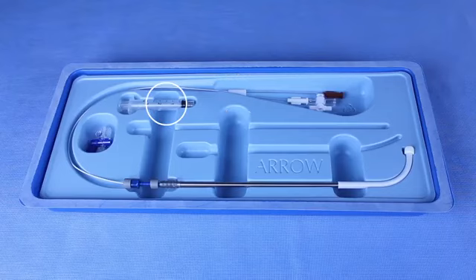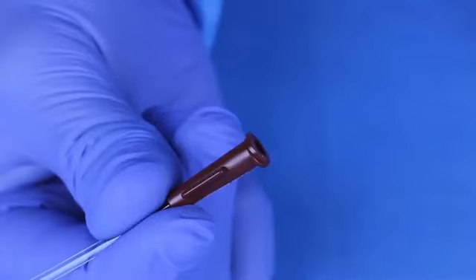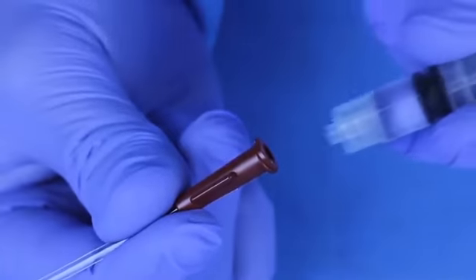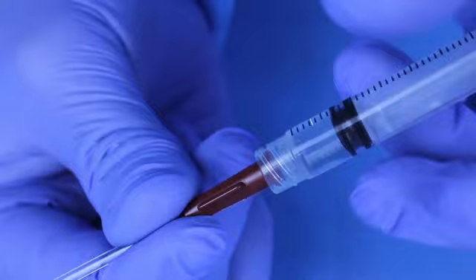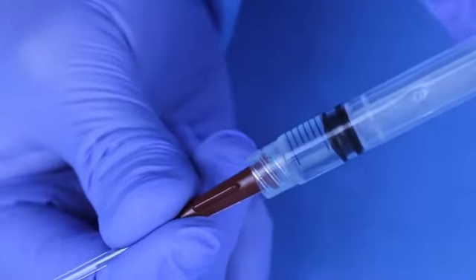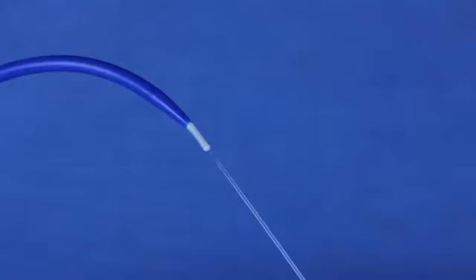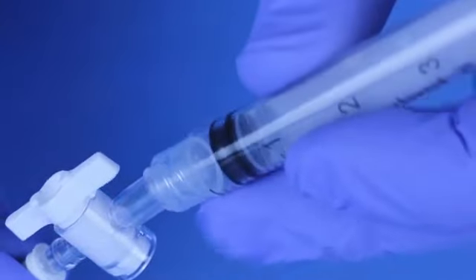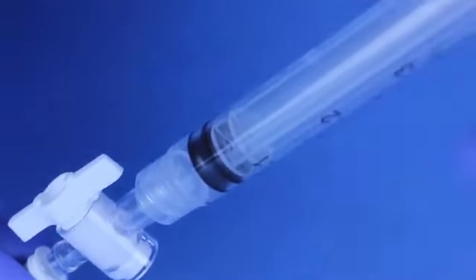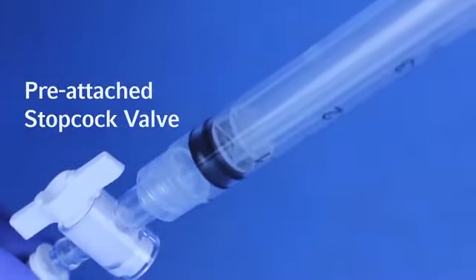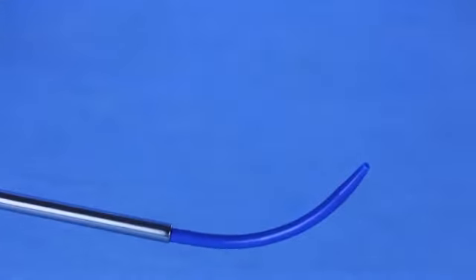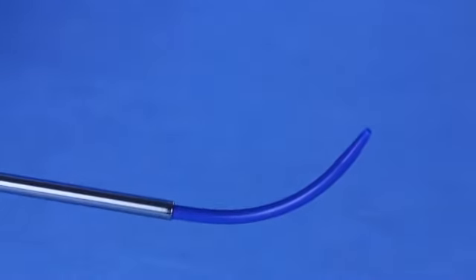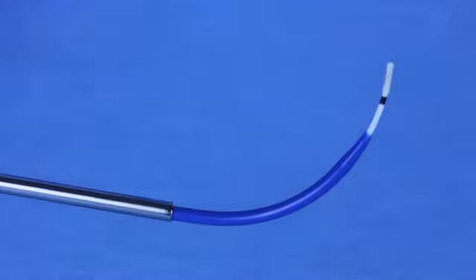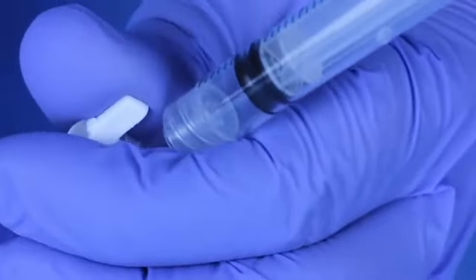catheter, 1 1/4 milliliter control stroke syringe, 3-way stopcock. Flush infusion port of balloon catheter and any attached tubing or stopcock with sterile saline. Be certain to remove all air bubbles. Connect syringe to balloon port on catheter. The balloon port can be identified by its pre-attached stopcock valve. Advance catheter so balloon is outside metal introducer cannula guide catheter assembly. Test balloon by inflating with air.